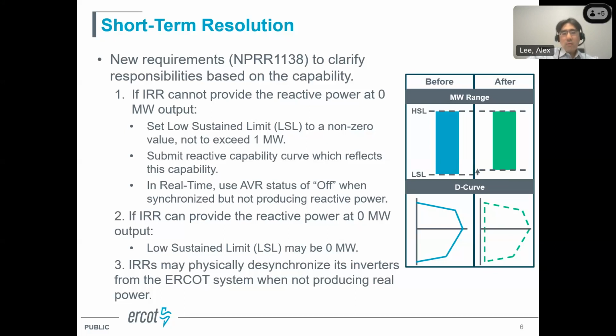ERCOT decided to apply a similar approach to IBR resources. The short-term focus has been: if IBR resources are not able to provide reactive support at 0 megawatt output, they should simply reflect that limitation in their model and have that information correctly delivered to ERCOT, so there's no gap between what ERCOT's information shows and what is actually capable in the field.